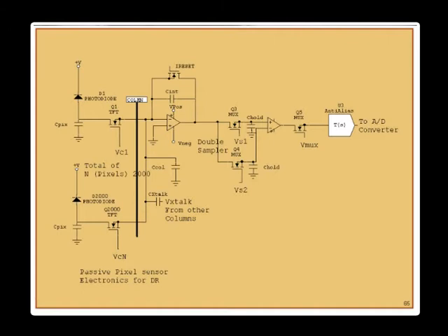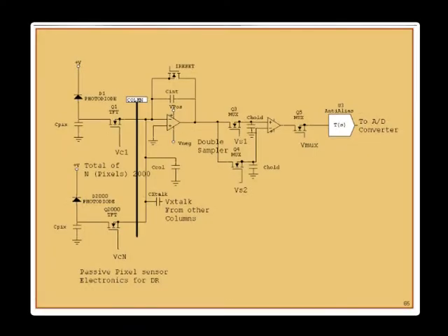Regarding the electronics: the photodiode is represented as an equivalent circuit with a pixel capacitor, a TFT switch, and there should be 2000 of them in an array. There is crosstalk from other columns and column capacitance. A correlated double sampler — a technique from charge-coupled devices — along with a multiplexer, anti-aliasing filter, and analog-to-digital converter complete the readout chain.